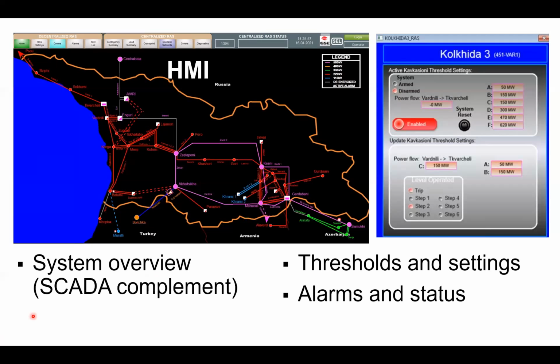It is very usual that some customers prefer to have ECS HMI screens in the SCADA system, which is for dispatching only. The SCADA is for dispatching only. We decided to have a separate HMI system providing data monitoring and control possibilities, and also, as Lado has mentioned, providing the ECS operator the possibility of changing set points in case of changing of power flow in the system.